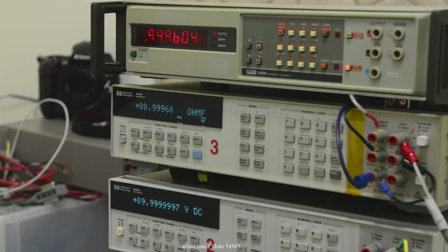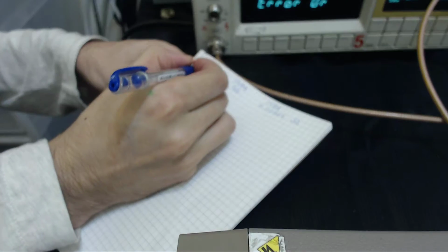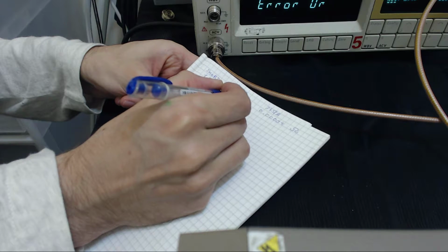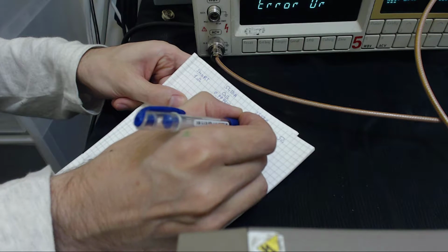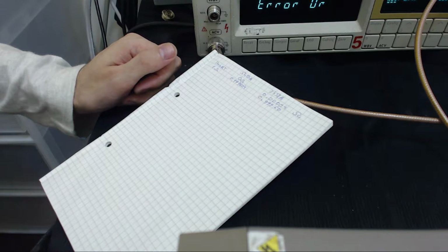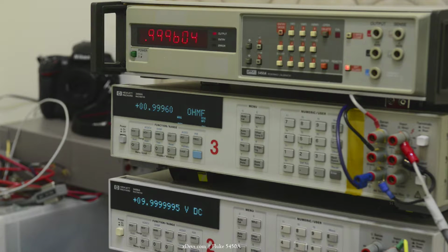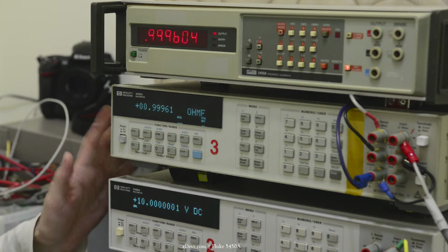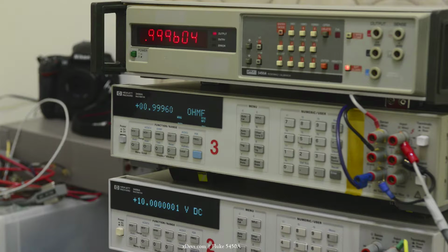Okay, this is a very nice match, we can write it down: 1 ohm, expected value 999,604, and the actual meter value is 999,60. Regarding the environment, I let everything warm up for a couple hours, and the meter is on 24/7 so it's never off. Room temperature right now is 24°C.